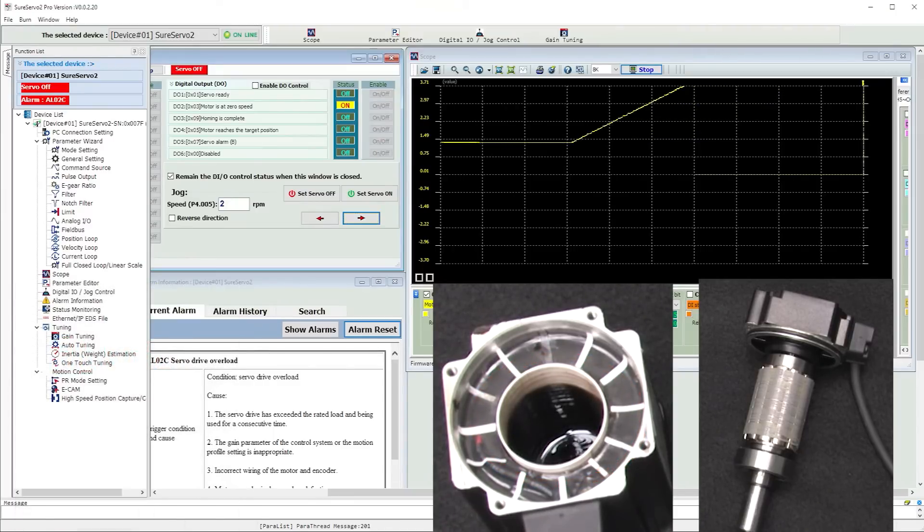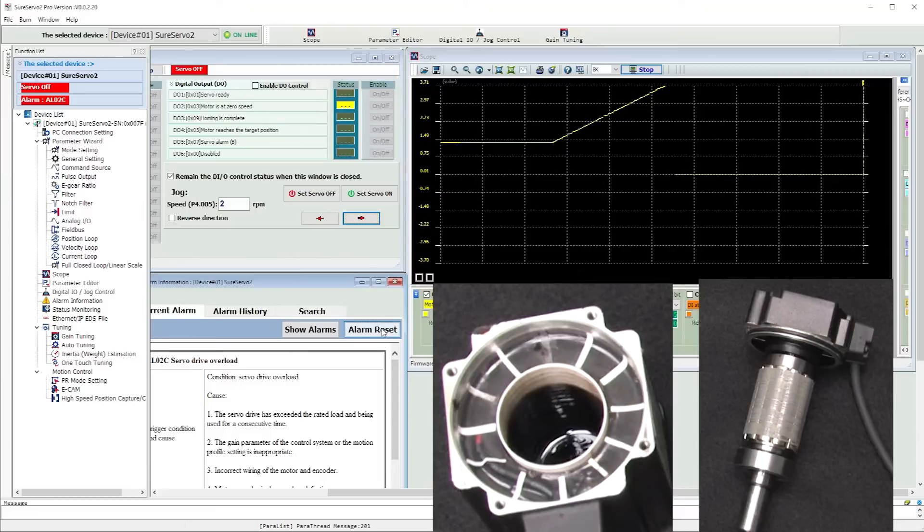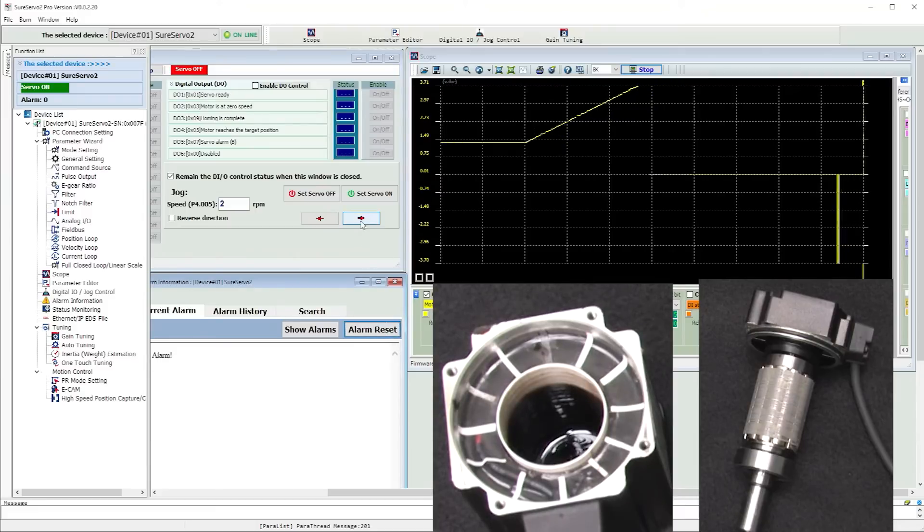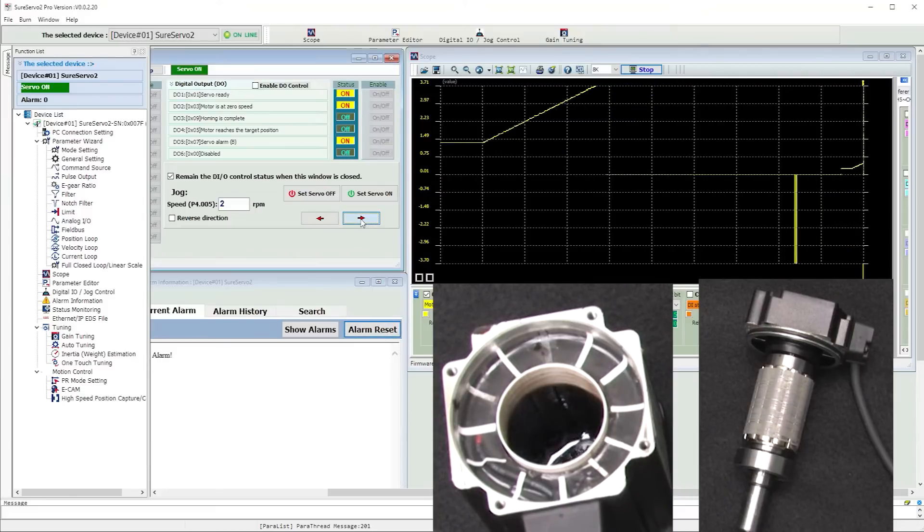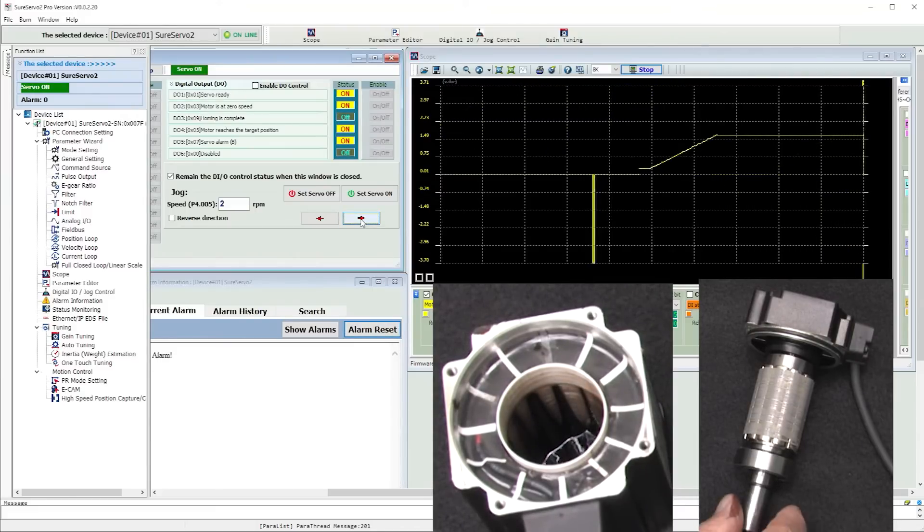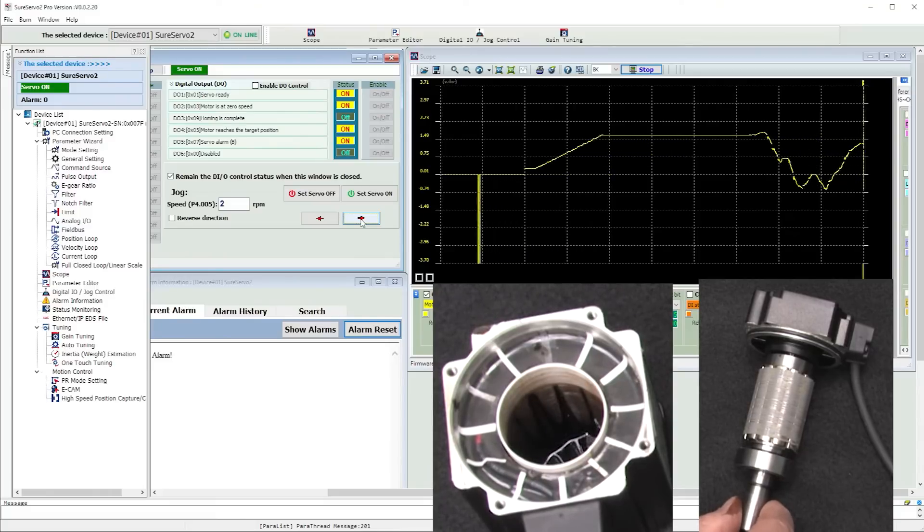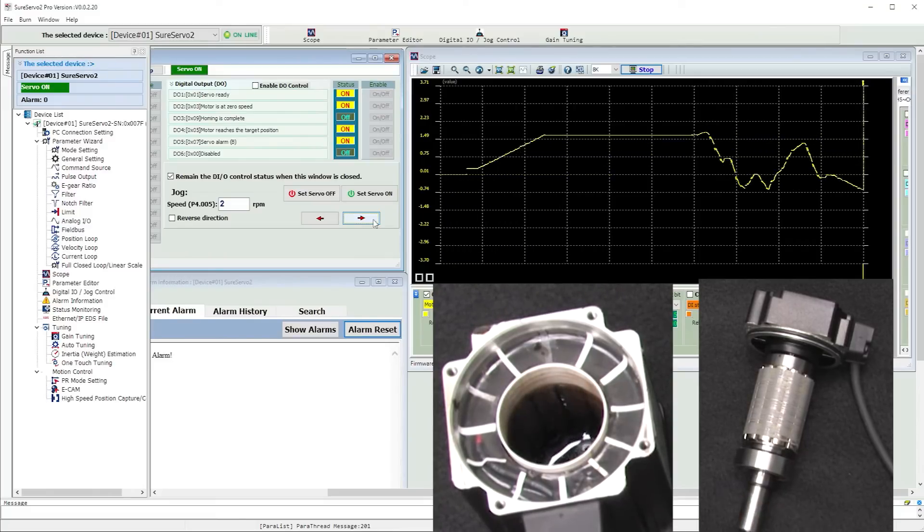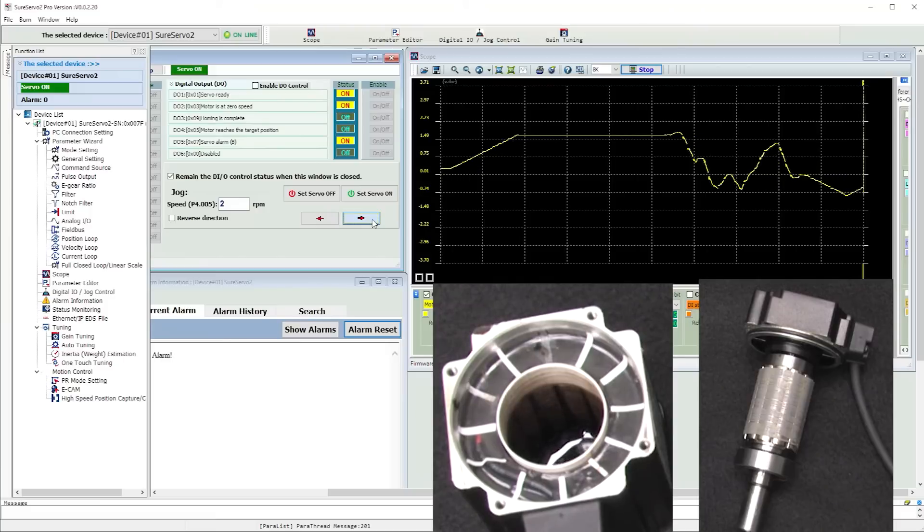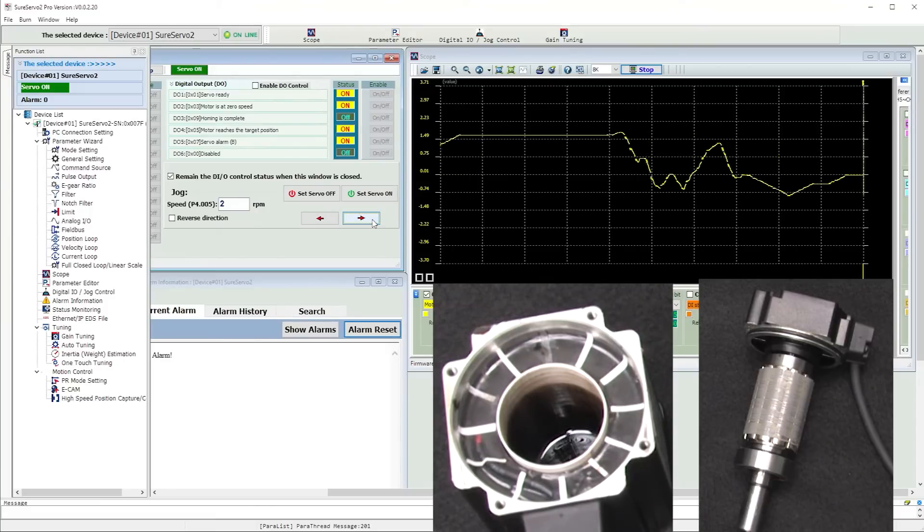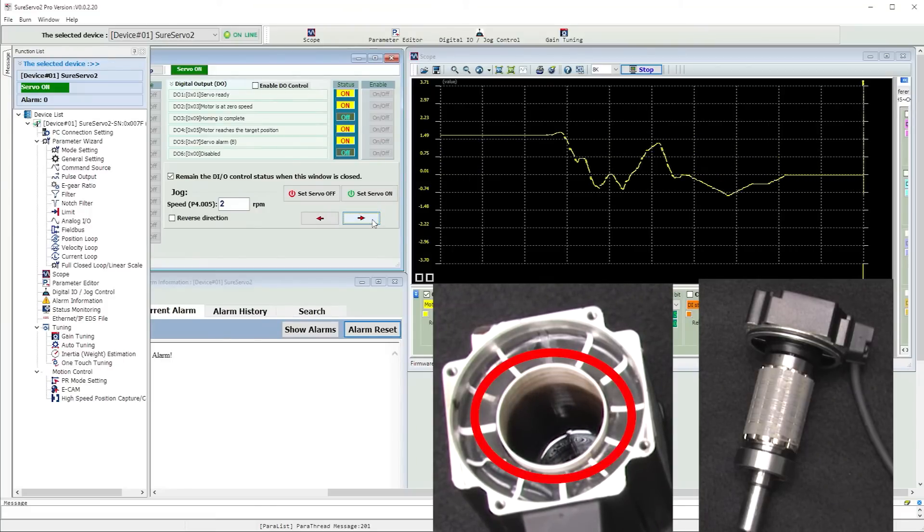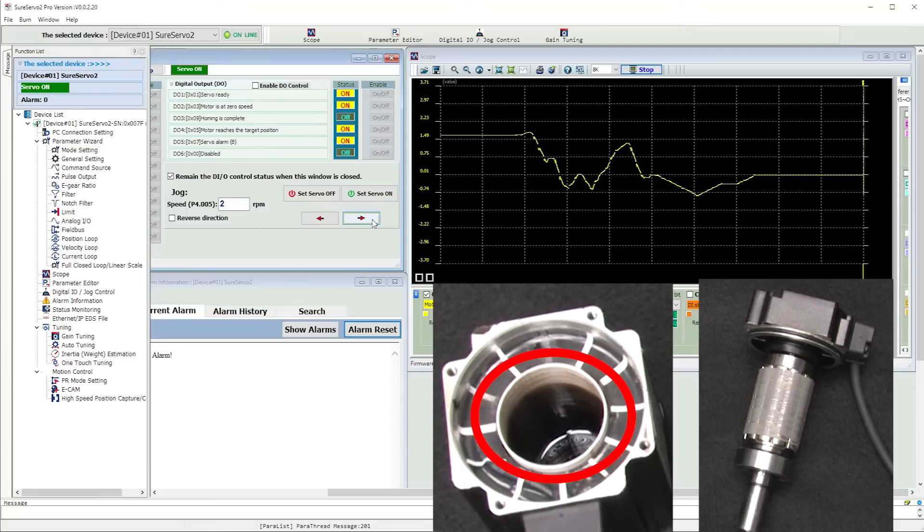OK, let's reset the fault and jog a bit to reestablish the magnetic field. If I gently rotate the rotor – really the encoder – in the direction the drive wants it to go, it's really touchy so I'll finish it off by jogging to zero amps, we see the current reduce and the magnetic fields drop. Perfect.